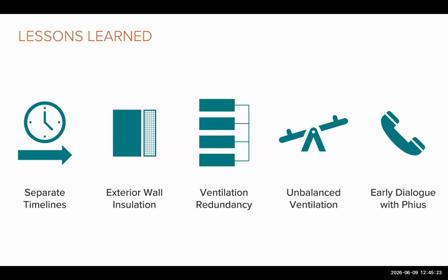Speaking of balance, unbalanced ventilation was a surprise that came up in the tenant fit out phase when coordinating the med gas ventilation and final calculations. As Kristen mentioned, Phius allows us to be up to 10% out of balance for the ventilation, and in design, we're at 7% for one of the ERVs. So that's something we have flagged and are following pretty closely in construction with the entire project team. Finally, early dialogue with Phius was so key. I think engaging Phius at the beginning of the project, specifically on the source energy limit, helped really align design decisions and avoid costly rework, contributing significantly to the project's success.